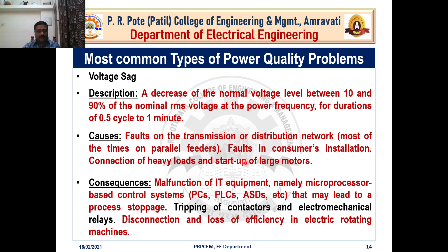Now let's see the standard definition of voltage sag. IEEE defines the voltage sag as a reduction in voltage for a short time. The duration of a voltage sag is less than 1 minute but more than 8 milliseconds, that is 0.5 cycle. And the magnitude of reduction is between 10% to 90% of the normal RMS voltage at 50 Hz. So this is the standard definition given by the IEEE for voltage sags.